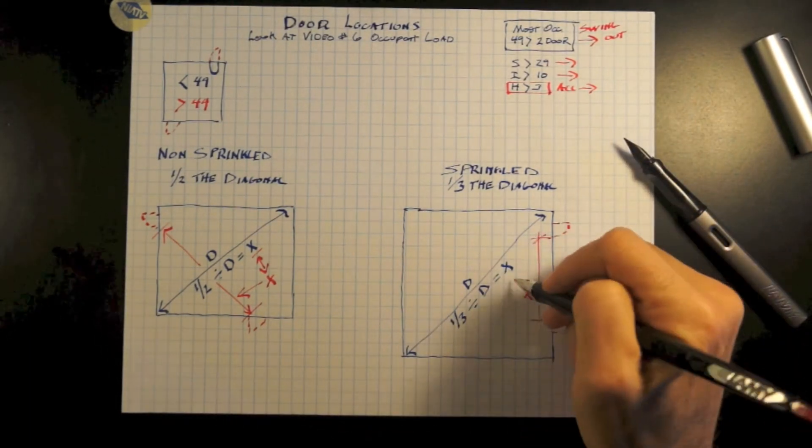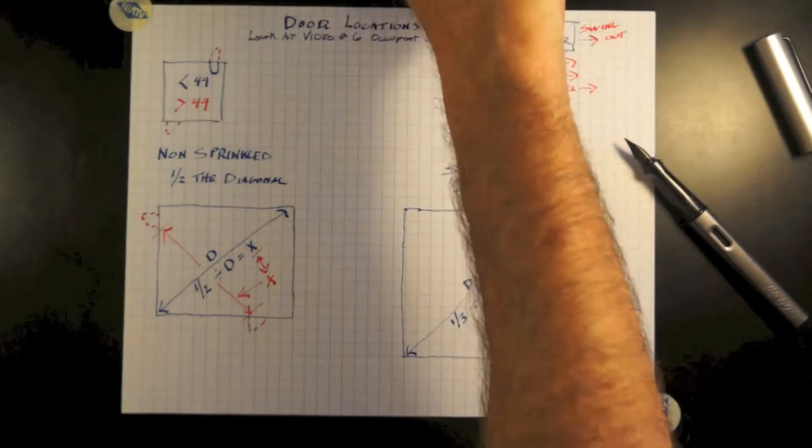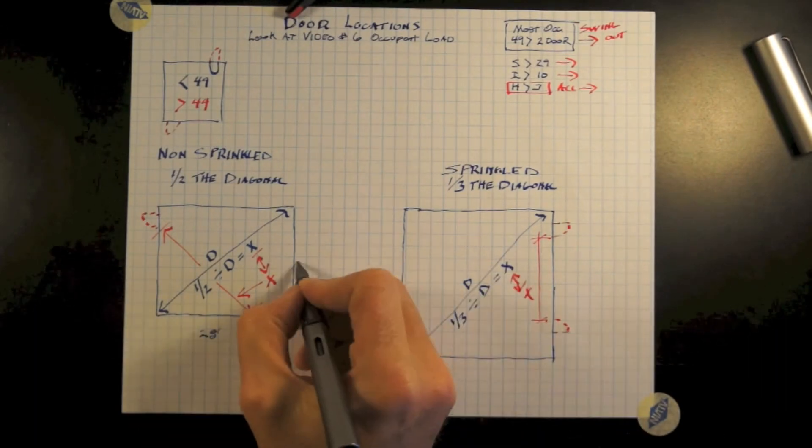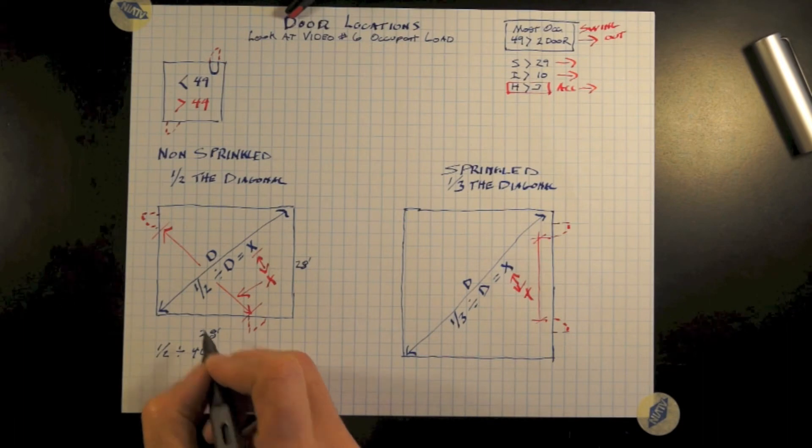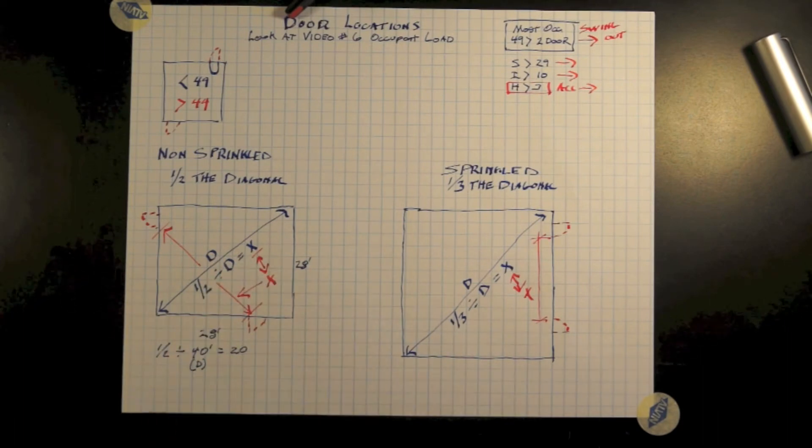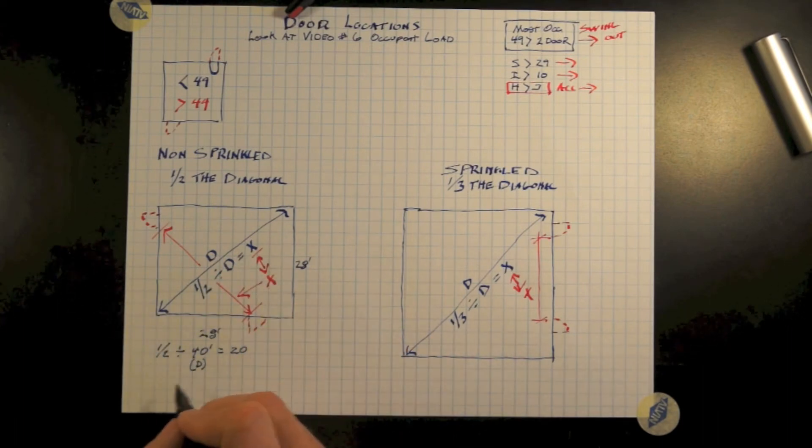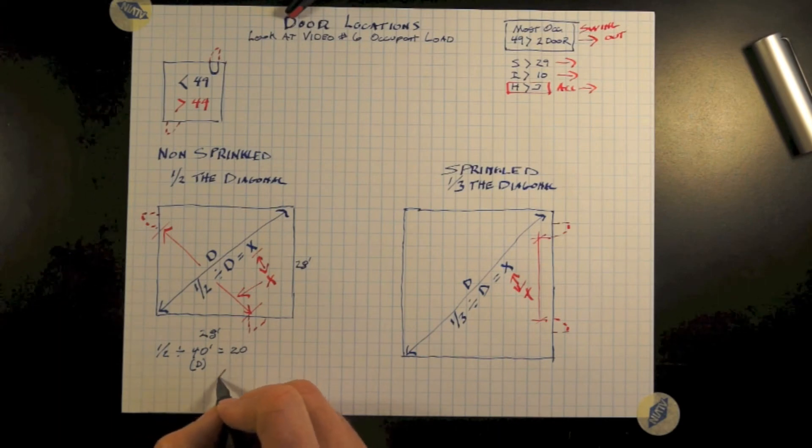Let's physically do the math. On a building or a room that's 28 by 28, our diagonal distance is going to be right at 40 feet. So one half divided by 40 feet equals 20. So X, the distance between the two doors shall be not less than 20 feet.